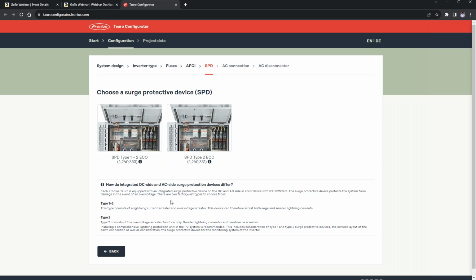But then for regions that don't have a high frequency of lightning, it could be advised to go for type 2. Because this same type 2 provides smaller lightning current protection. But then for regions, tropical regions for example, that have high rates or frequency of lightning, it is advised to go for type 1+2 protection, as it provides protection for both large and smaller lightning currents. So continuing, let's say we select type 1+2 protection.